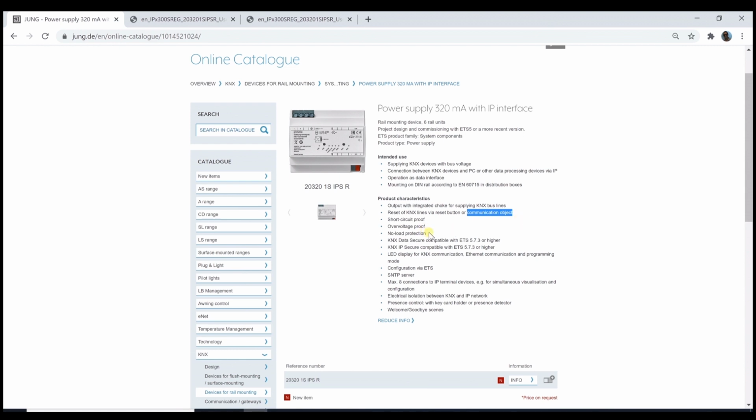Of course, general features like short circuit proof, overload and overvoltage proof, as well as a no-load protection, you find on board here as well, but those are general features. Very important, of course, because it's a new item, you find Data Secure compatibility as well as IP Secure compatibility. Means the new communication by KNX is supported by this device.